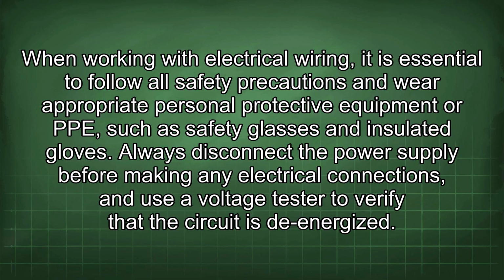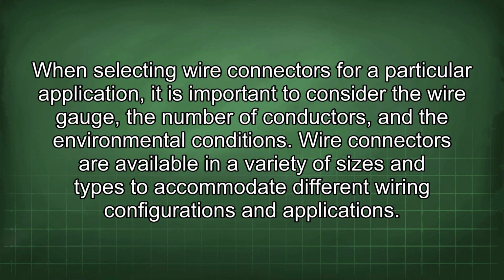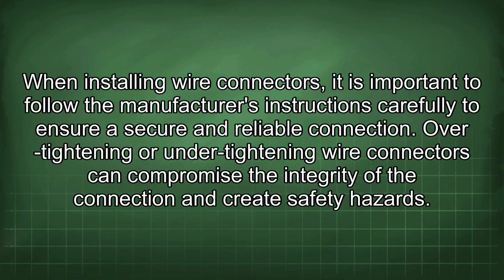Always disconnect the power supply before making any electrical connections, and use a voltage tester to verify that the circuit is de-energized. When selecting wire connectors for a particular application, it is important to consider the wire gauge, the number of conductors, and the environmental conditions. Wire connectors are available in a variety of sizes and types to accommodate different wiring configurations and applications. When installing wire connectors, it is important to follow the manufacturer's instructions carefully to ensure a secure and reliable connection. Over-tightening or under-tightening wire connectors can compromise the integrity of the connection and create safety hazards.